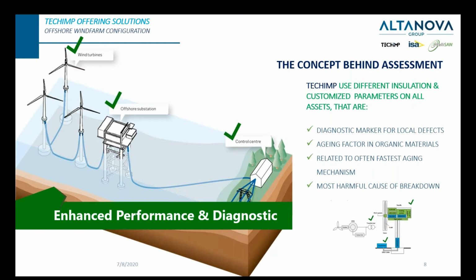Here are some factors that we need to figure out. For example, we should have proper diagnostic markers to discriminate the defects. The diagnostic markers are the measured parameters such as temperature, humidity, voltage, current, capacitance, those kinds of things. And of course, when we are doing the diagnostic testing, we're talking about something like dielectric loss or partial discharge. In our webinar here, we are mainly focused on partial discharge diagnosis, but we will also cover the other technologies or diagnostic markers, such as dissolved gas analysis, dielectric loss, or the change of capacitance in specific applications, such as for transformers.